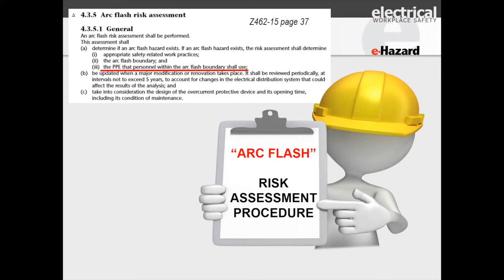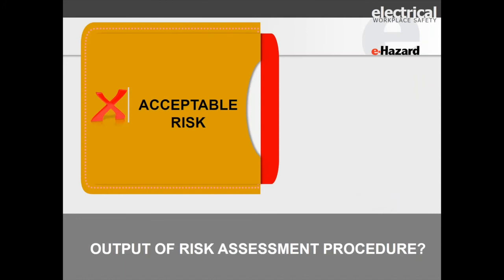The arc flash boundary, of course, is the onset of a second-degree burn at 1.2 calories per centimeter squared. And there it is again, topic of the day. What's the PPE that the personnel within the arc flash boundary shall use? And that's what you'll get in the arc flash risk assessment procedure, be it the PPE category method or the incident energy analysis method.